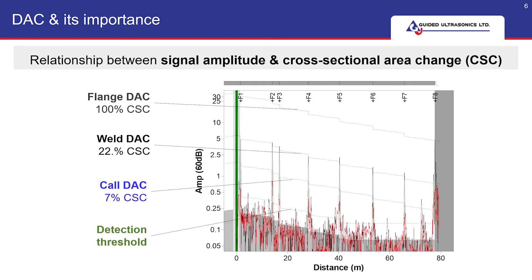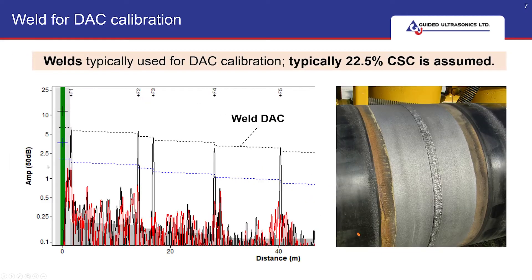DACs are not only important to account for the effects of reflection and damping, but they also provide a link between signal amplitude and the cross-sectional area change. So on the A-scan, the DACs are represented by the dashed lines. By default, there are three main DAC curves, which are the flange, weld, and call DACs. Typically, pipe circumferential girth welds are used for weld DAC calibration and are assumed to be 22.5% cross-sectional area change.